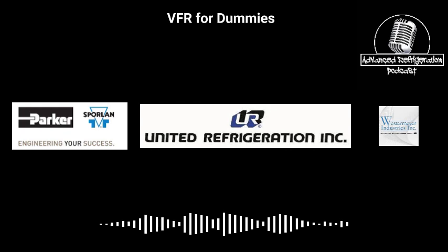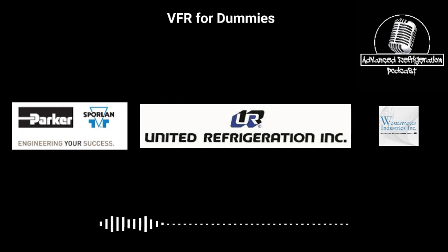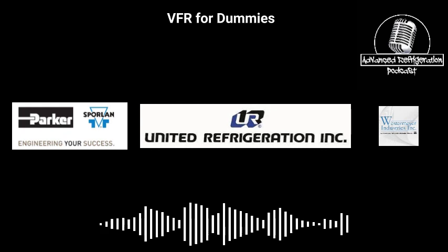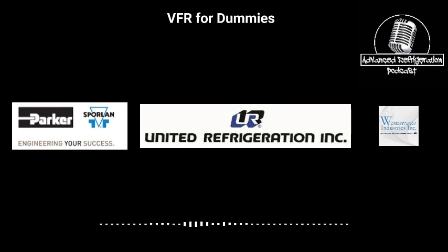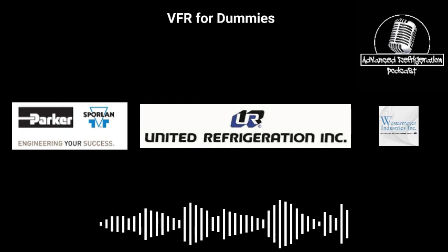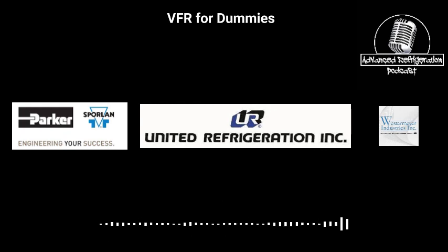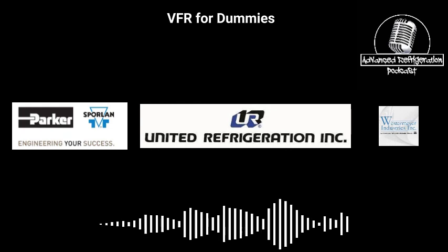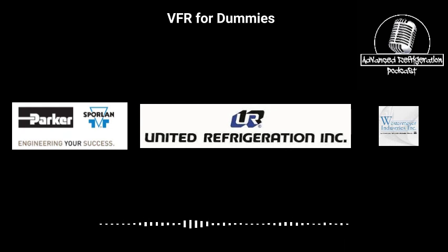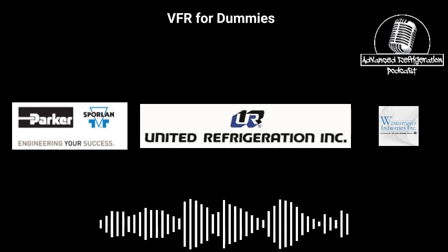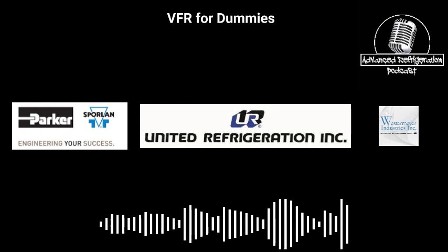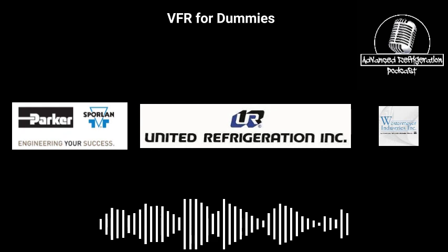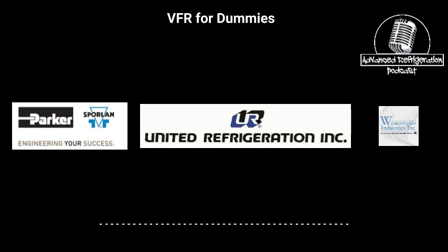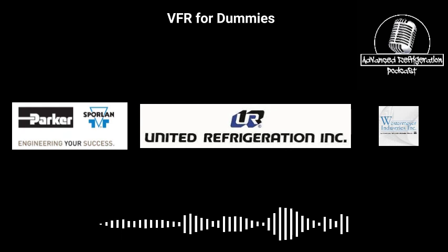So all right, the indoor unit has two expansion valves or three expansion valves? One. Just one. I think some Mitsubishis have two, but all the Daikin units have one. Well, the one you just showed me is a branch selector box. Oh, okay. That 12-port. I'm assuming it works like a 3-way valve, the switch from hot gas to liquid flow. They're probably using the EEVs, that way they can mix it. Does that sound kind of correct?